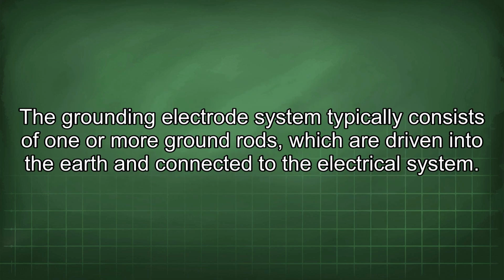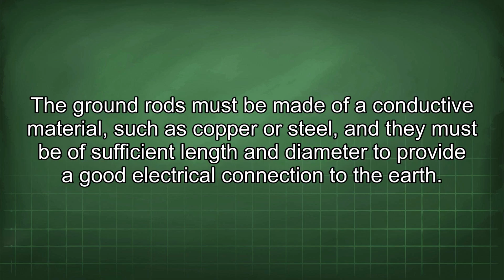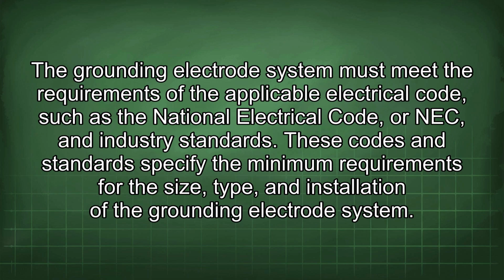The grounding electrode system typically consists of 1 or more ground rods, which are driven into the earth and connected to the electrical system. The ground rods must be made of a conductive material such as copper or steel, and they must be of sufficient length and diameter to provide a good electrical connection to the earth. The grounding electrode system must meet the requirements of the applicable electrical code, such as the National Electrical Code, or NEC, and industry standards.